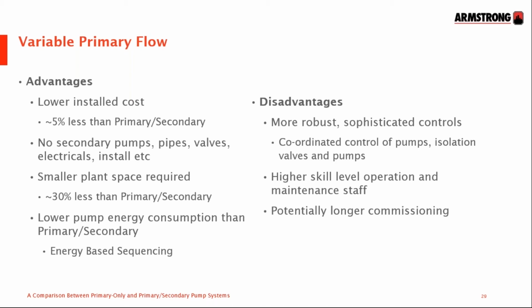The downsides of variable primary flow: you need to have a robust and sophisticated control system. We talked about all the ups and downs of the controls, the valves, the bypass valve, the chiller valves, and the load valves as well. And the staff operating it need to be arguably a higher skill level than those for a primary secondary. And to get the valve settings correct, you need to spend a little bit longer commissioning the system.